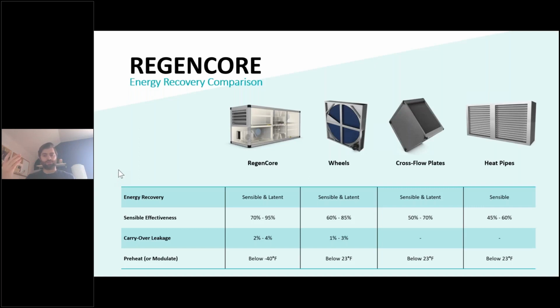So comparing it to other energy recovery technologies, the huge benefit with RegenCore is the sensible effectiveness, usually around 90–91%, and the no requirement for preheat, down to -40. So we've tested this within our climate chamber, and the unit still works at the expected sensible effectiveness, all the way down to -40 without any preheat.